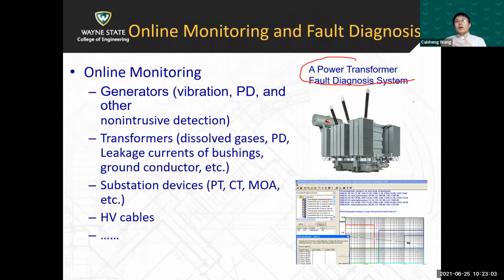Then the system will tell you what the problem might be, or if there's any problem, or if everything's okay. If something's wrong, the system will tell you what further action you might need to take—for example, doing some dissolved gas analysis, taking an oil sample, or running partial discharge tests.